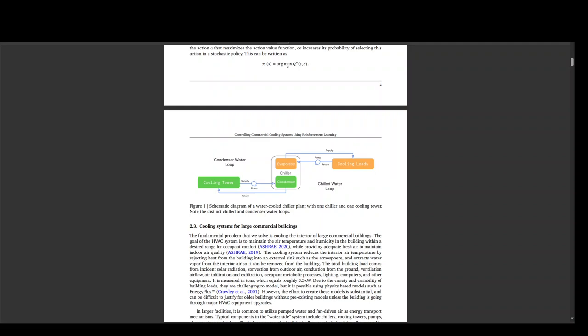These authors, as part of this research, also collaborated with domain experts to determine a chiller plant's potential actions and states. And then these authors trained the ensemble on a year's worth of data from the chiller plant heuristic controller via reinforcement learning. And then for 3 months, they alternated between controlling the chiller plant using the ensemble for 1 day and the heuristic controller for the other day.